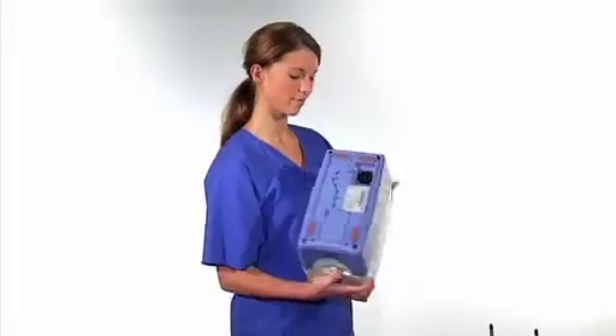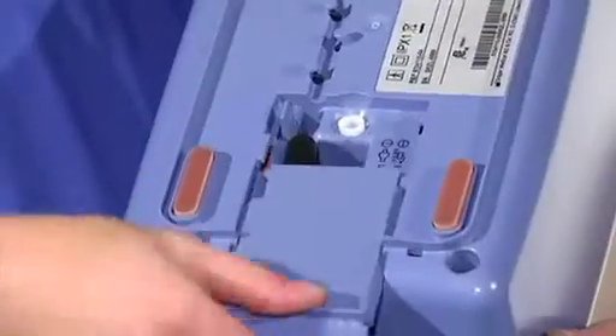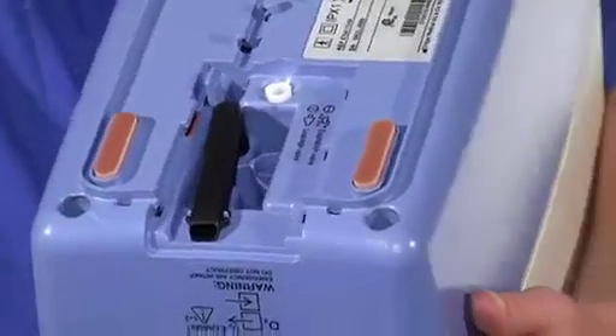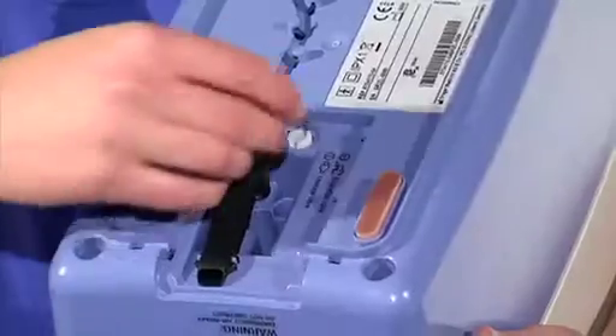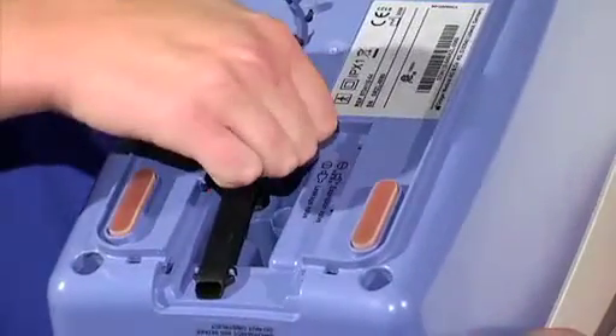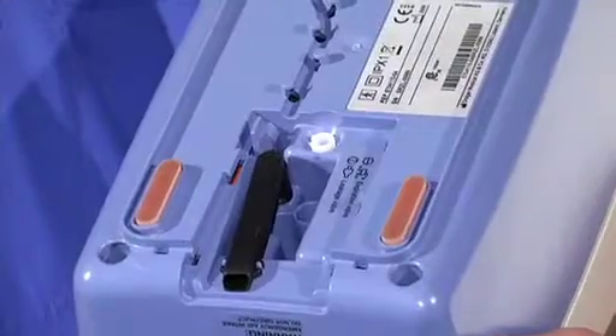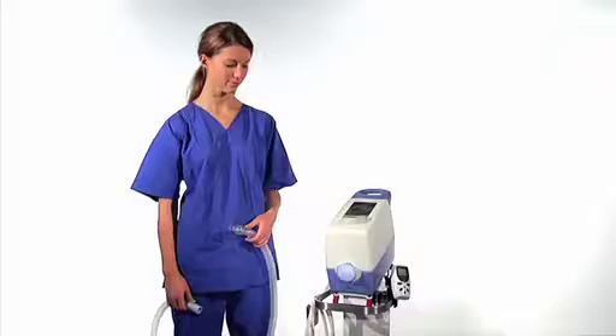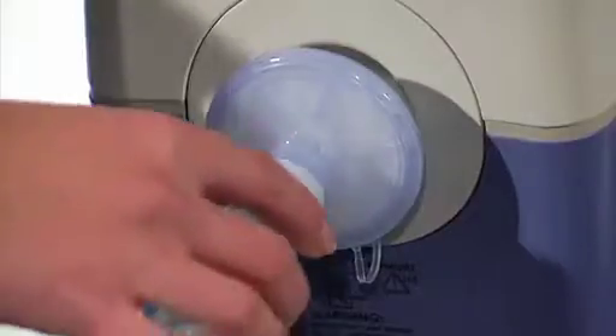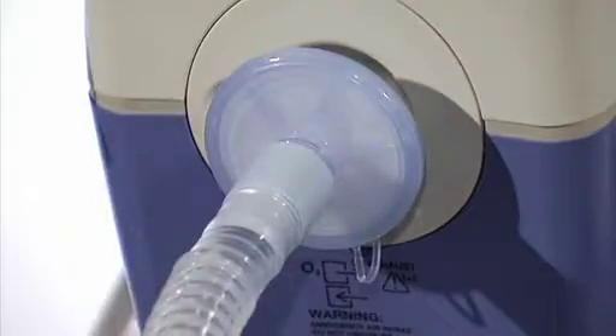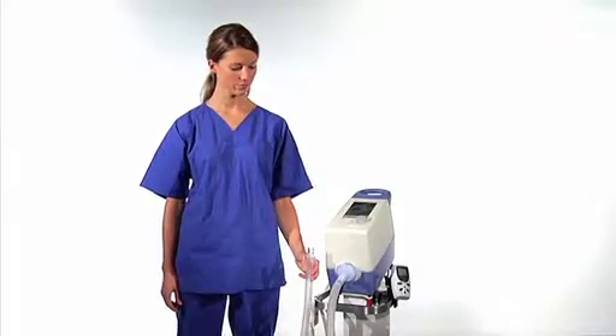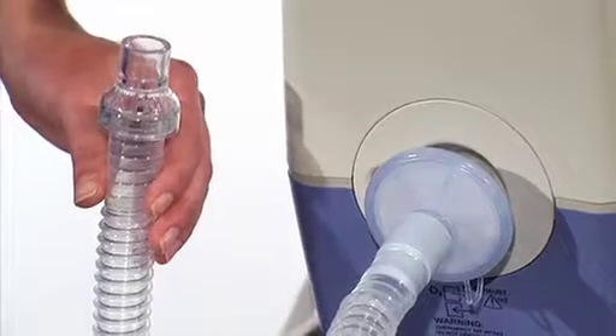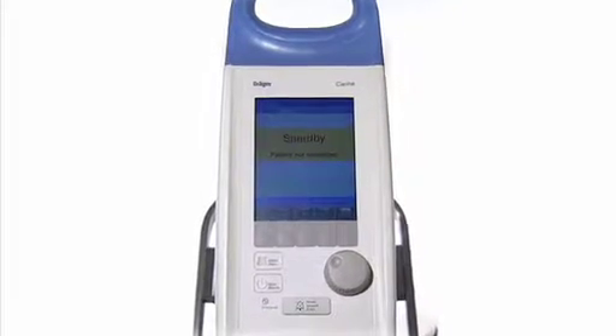A selector switch located on the bottom of Carina needs to be adjusted according to the type of valve in use. Switching is fast, but ensure that a properly trained staff member chooses the correct setting. Using the leak valve circuit allows broader application for invasive and non-invasive ventilated patients. Now let's take a look at Carina's front panel.